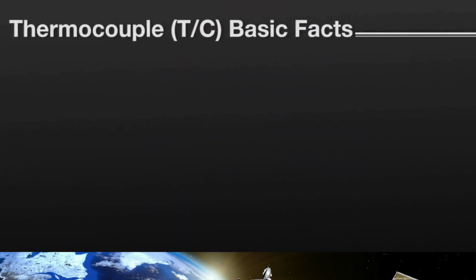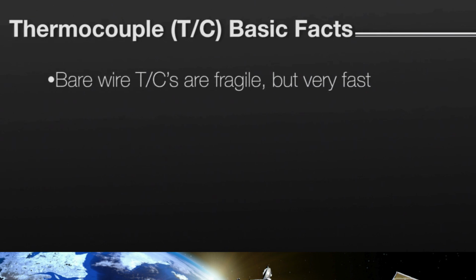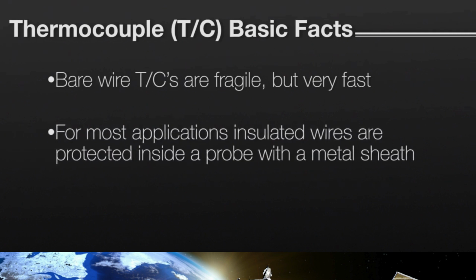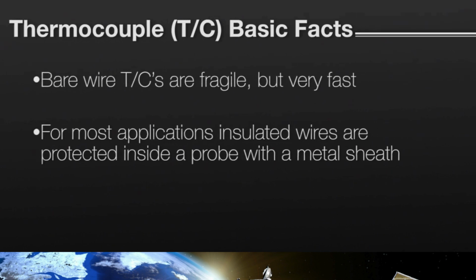Bare thermocouple wires range in diameter from 0.1 to 3 millimeters. The smaller ones are very fragile, but they'll give you a fast response time when heated. Unless you need response times well under 1 second, you will want to buy a thermocouple protected inside a metal sheath, possibly with ceramic insulation between the wires. Otherwise, it won't last very long when you use it to measure temperatures over 1,000 degrees C.